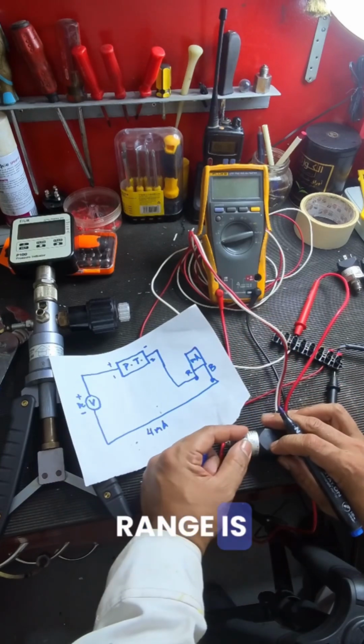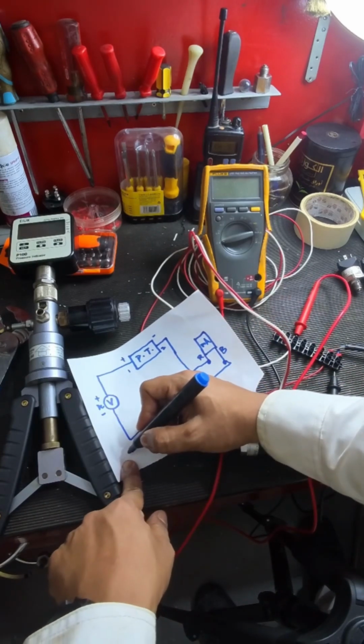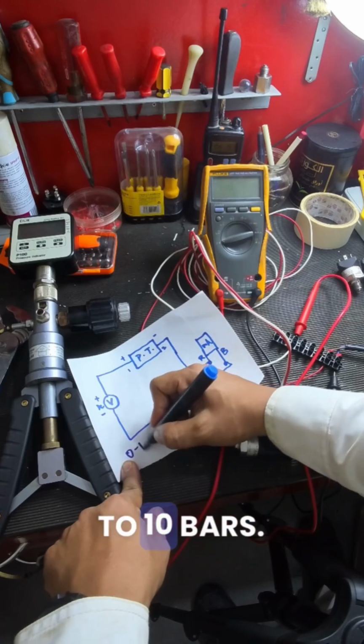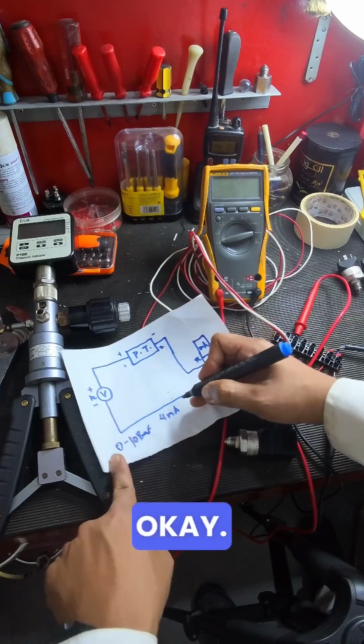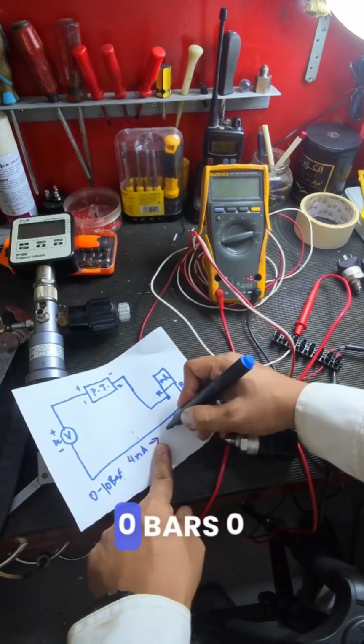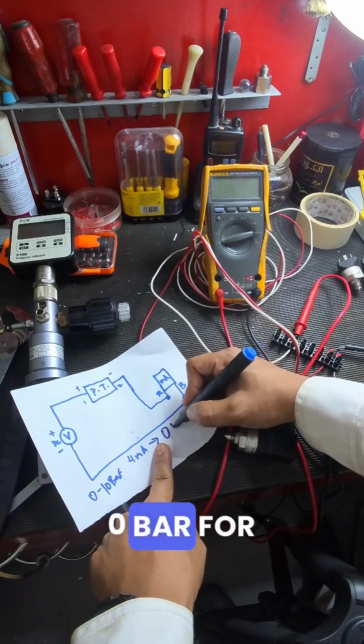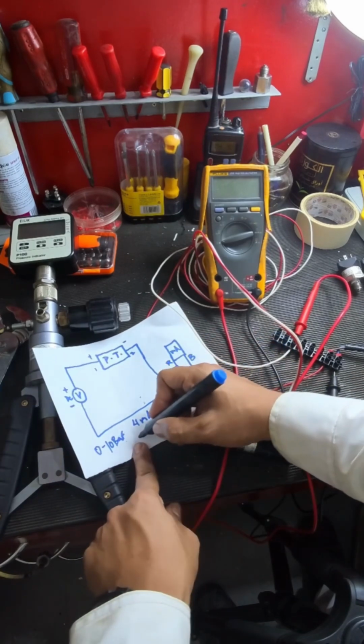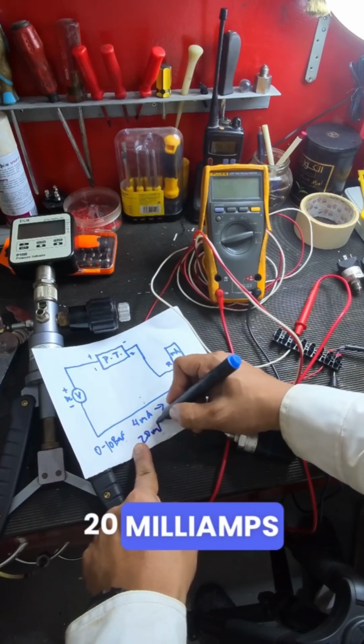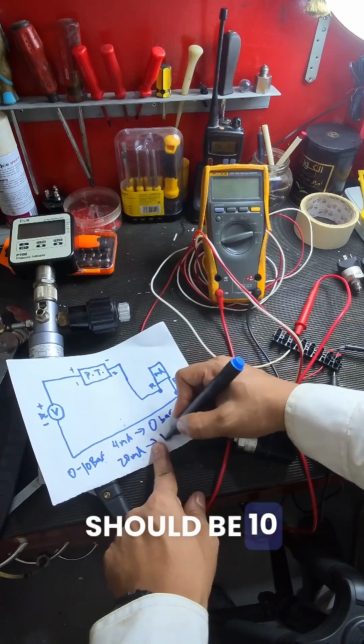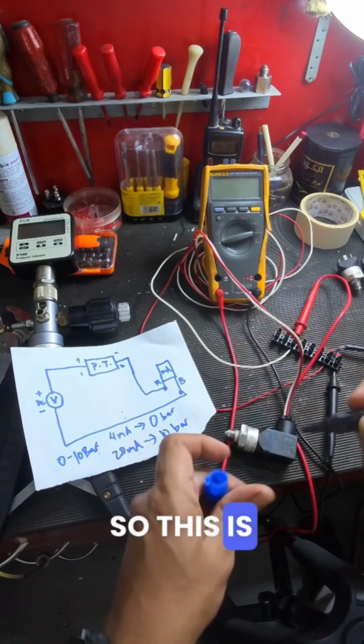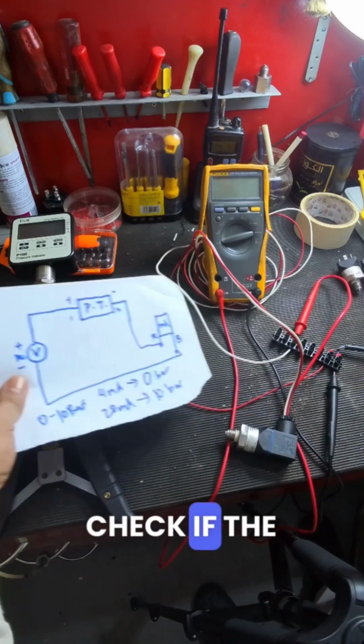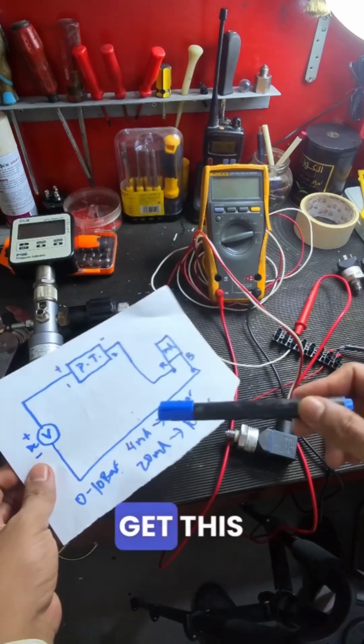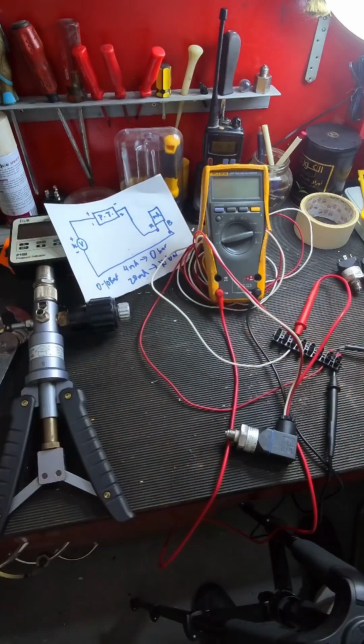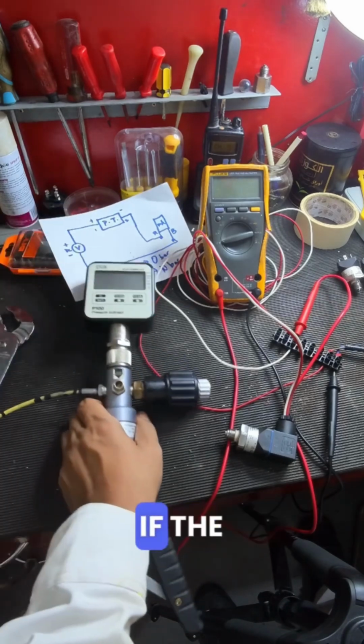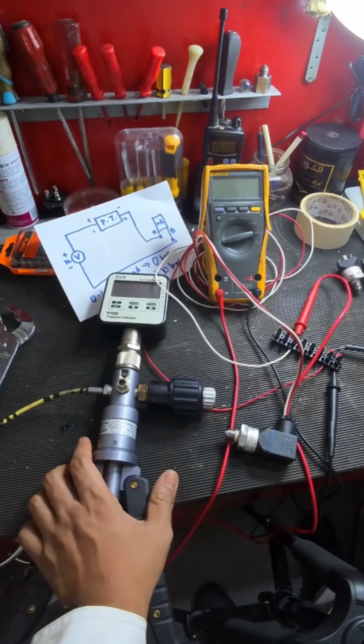For example, the range of the pressure sensor is 0 to 10 bars. So 4 milliamps should be at 0 bar, 0 pressure. For the output signal, 20 milliamps should be 10 bars. So this is what we need to check, if the pressure sensor will give this output signal. That's the time you can identify if the sensor is good or bad.